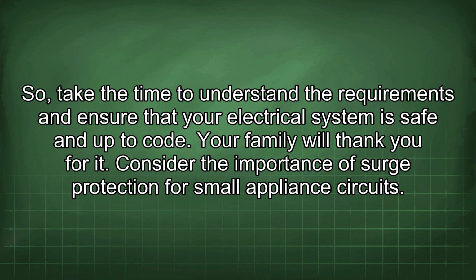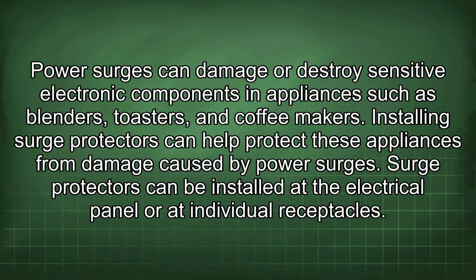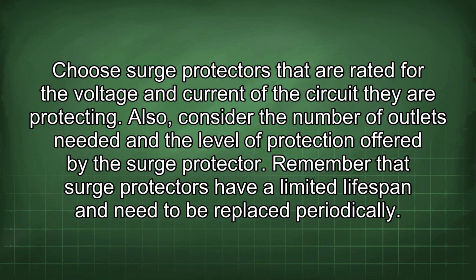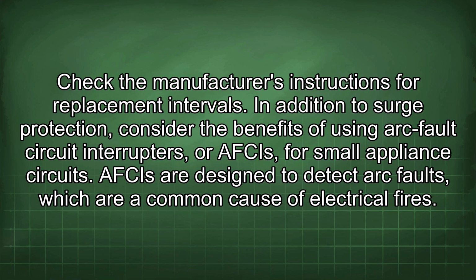Consider the importance of surge protection for small appliance circuits. Power surges can damage or destroy sensitive electronic components in appliances such as blenders, toasters, and coffee makers. Installing surge protectors can help protect these appliances from damage caused by power surges. Surge protectors can be installed at the electrical panel or at individual receptacles. Choose surge protectors that are rated for the voltage and current of the circuit they are protecting. Also, consider the number of outlets needed and the level of protection offered by the surge protector. Remember that surge protectors have a limited lifespan and need to be replaced periodically. Check the manufacturer's instructions for replacement intervals.